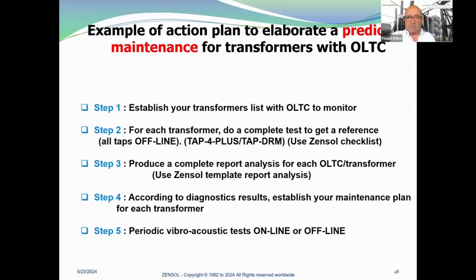Step 3, produce a complete report analysis for each OLTC transformer. So we have developed also a Zensol template report analysis. And so I can guarantee that at the end of this report, you will understand exactly how your tap changer is operating. And step 4, according to diagnostic results, you can establish your maintenance plan for each transformer.